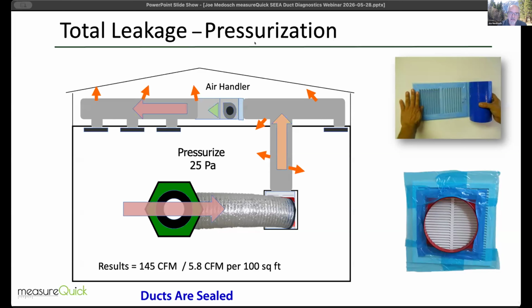And I now am in the HVAC world and out of more of the energy and IEQ, and I'm stunned at the few people that are actually testing their ducts, evaluating airflow, or doing anything to figure out what are the real problems, because the boxes are usually fine. It's how do I get from A to B that's actually causing all the issues. So this was kind of a major disappointment, the amount of people that are really assessing that. And there are some great folks on this call that are in the background that do this and do this well. So chime in if you got advice about how you could recommend other contractors.